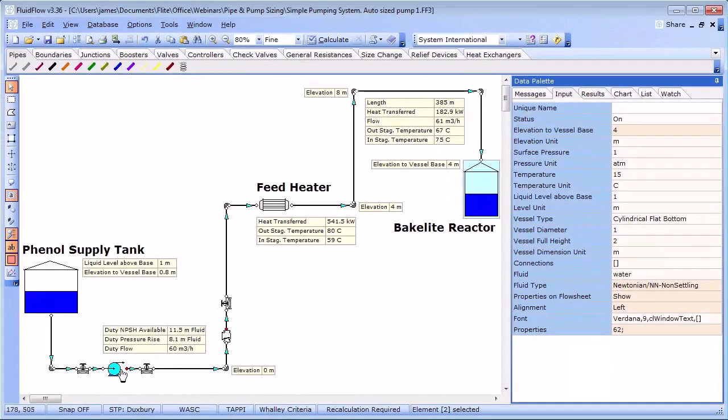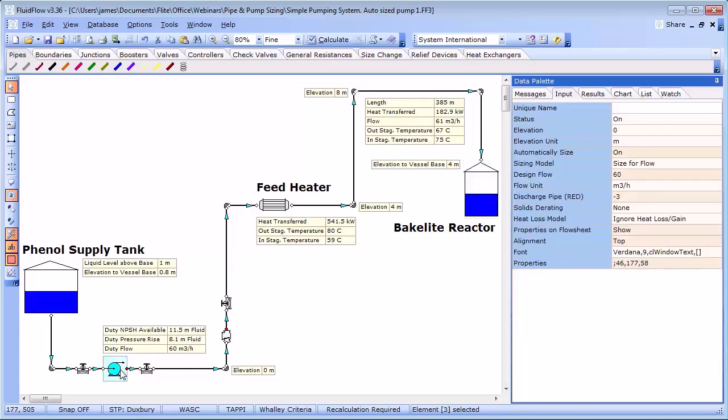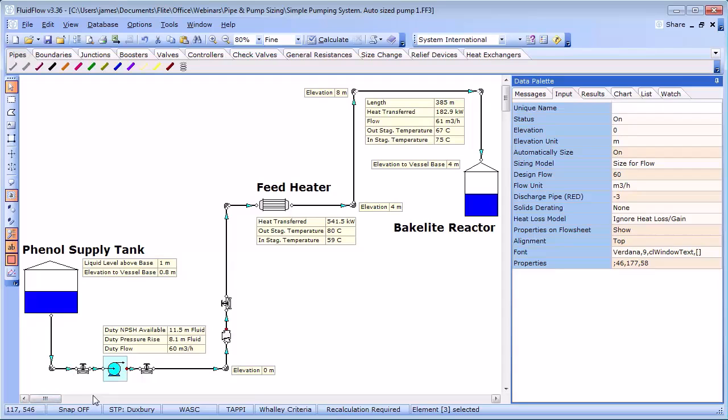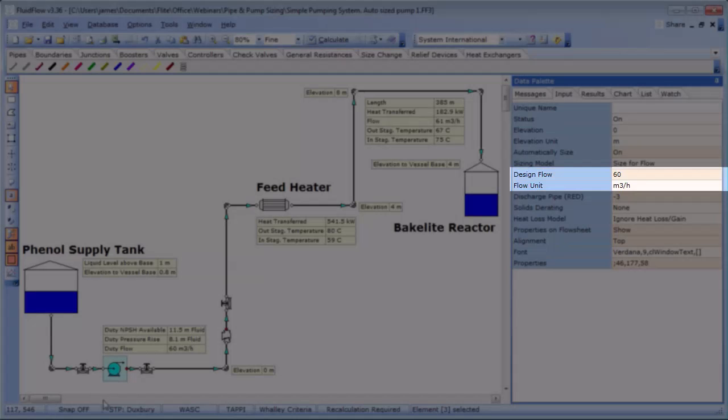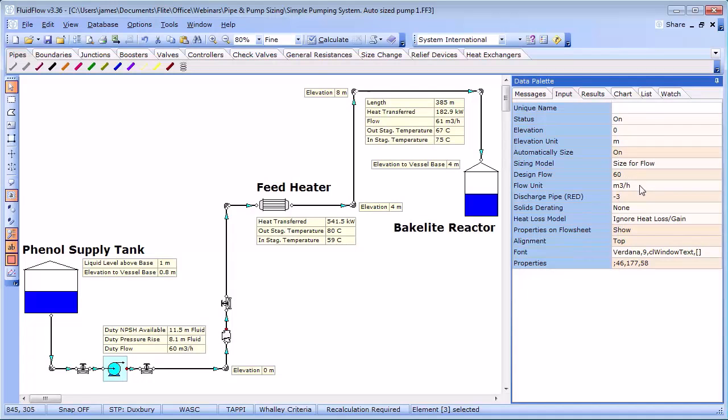Using this design flow rate we will consider how to size the pipes, size the pump and determine the actual mechanism for achieving our design flow and also consider pipe heat loss. At this point in the process you may ask yourself, where do I start? To size any pump or compressor, transport any fluid, the first two steps we should consider are: define the flow rate that the pump is required to deliver, which is usually determined from the design mass balance of the process. The second step is to determine the total differential head that the pump must generate in order to deliver the required design flow rate. Since the head any pump will develop is dependent on the piping system and elevation differences, we can immediately recognize that it is impossible to size a pump without considering the piping system.